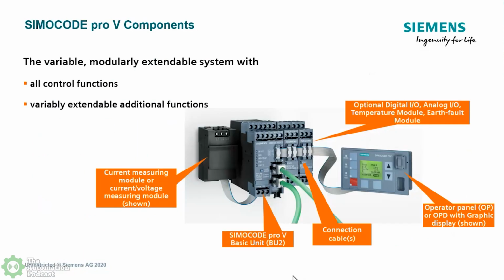So quickly, we'll just kind of go through. Here's kind of the basic setup. As I stated, the basic unit is your CT module. Let's just say for our discussion today that our customer wanted to monitor his voltage and current. It's a little bit of an eye chart, but L1, L2, and L3 is right there in the front. That's where you wire in the voltage. And then the current for this CT module is a pass-through, where you feed the wires through. We do have a bolt-on version. And then there's a cable, and then it goes to the basic unit.